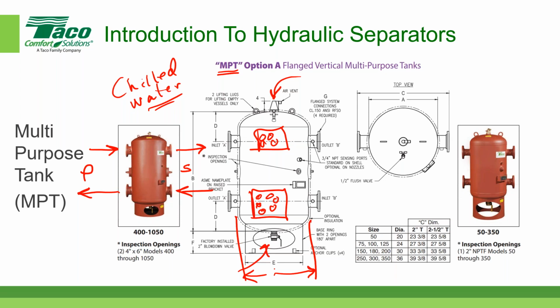So chilled water is a little bit critical, so you have to look at that carefully and make sure that you're not going to get any mixing. Generally, with hot water, you can withstand some mixing, and it's not going to be detrimental to the operation of the system. So hot water is okay. Chilled water, you must check with the factory and make sure that it's not too large a diameter to operate without a lot of mixing. Is this another way to add volume to the system as well?